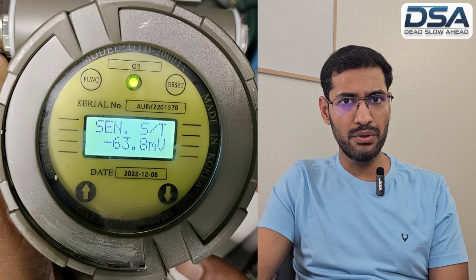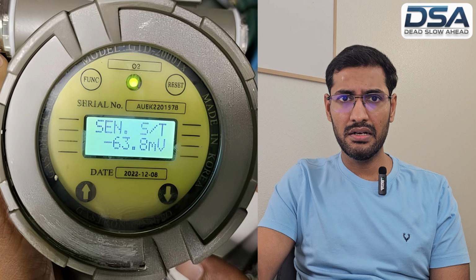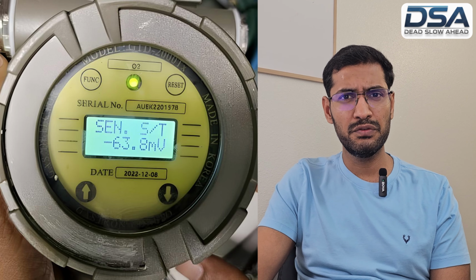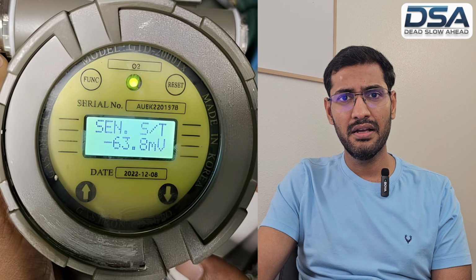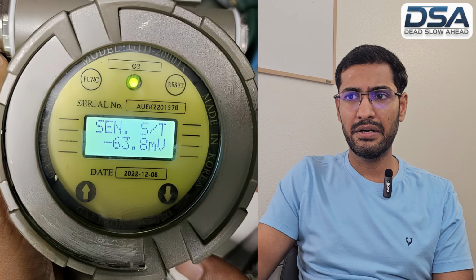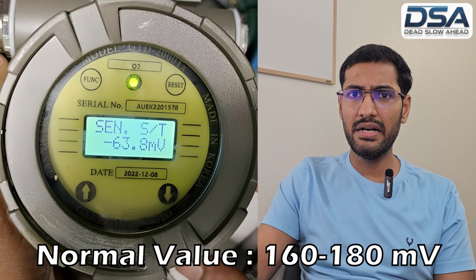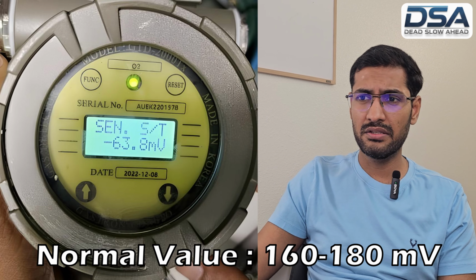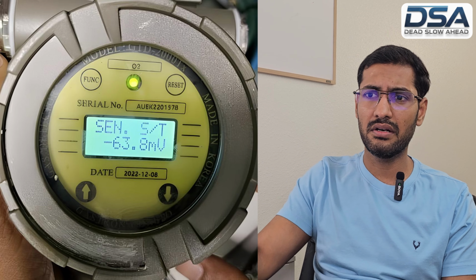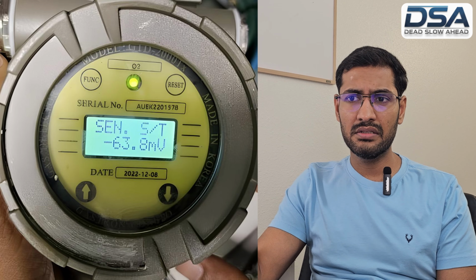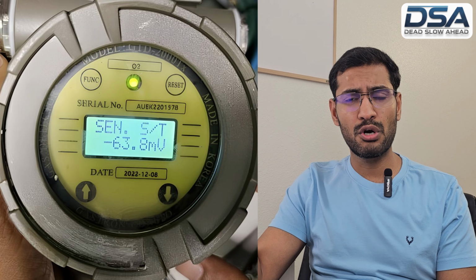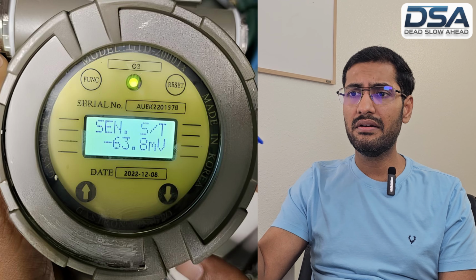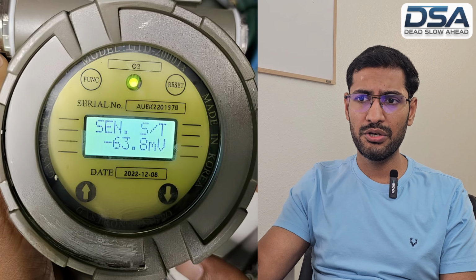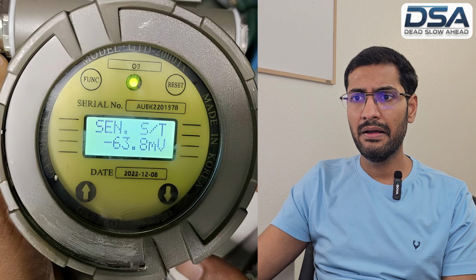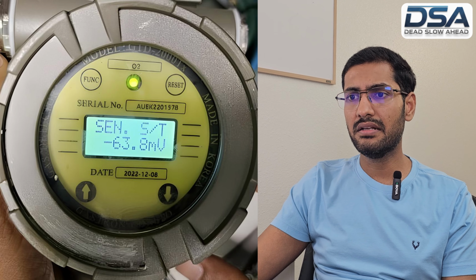Then we checked a very important parameter, the sensor ST voltage. Just for information, in a Gastron sensor the ST voltage is a very important parameter to check. Ideally it should lie between 160 to 180 millivolt, but in our case it was much lower than the required range. When the sensor ST voltage drops significantly below the normal range, we clearly concluded that the sensor is faulty and the only solution was sensor replacement.